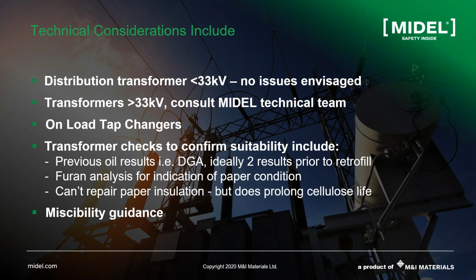And of course, finally, once we assess that this is a good voltage class, we ask the user to take DGA samples of that transformer. Best is 2 samples prior to retrofilling. Assess the furan analysis and the DP value of the paper, the insulation material inside the transformer. If the transformer is too old, we usually do not recommend retrofilling it because the user will not really benefit from or utilize the investment. It is worth emphasizing that esters, though they slow down aging mechanisms in the transformer, will not fix the paper. So if the paper is too old, then unfortunately it is too old, and perhaps buying a new transformer is the right option.